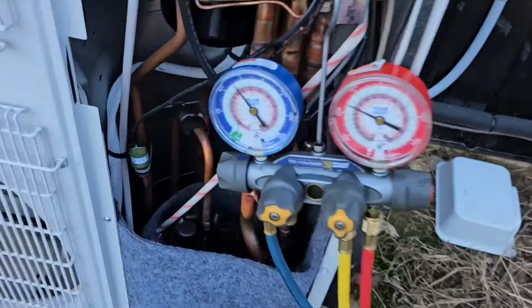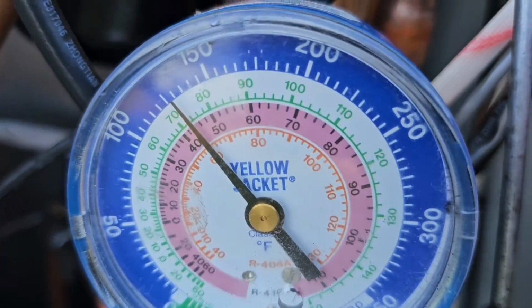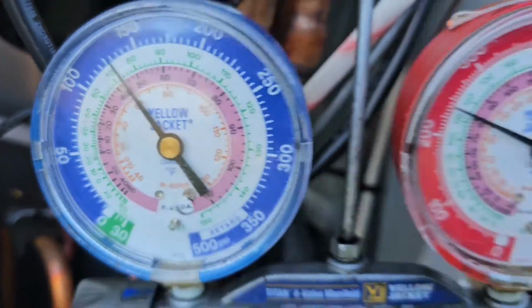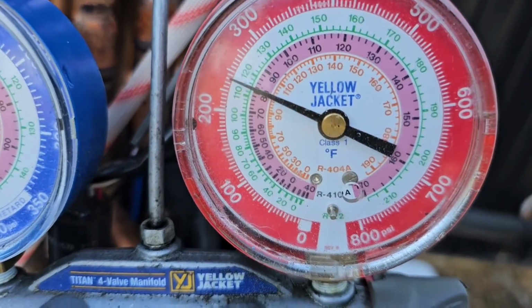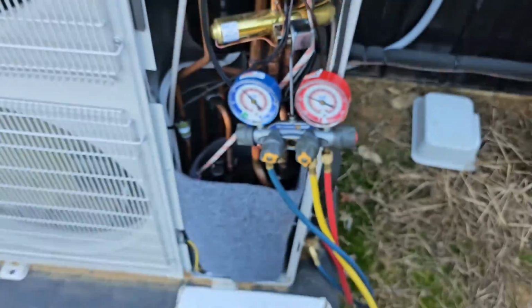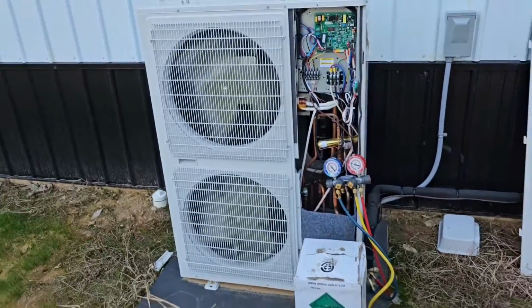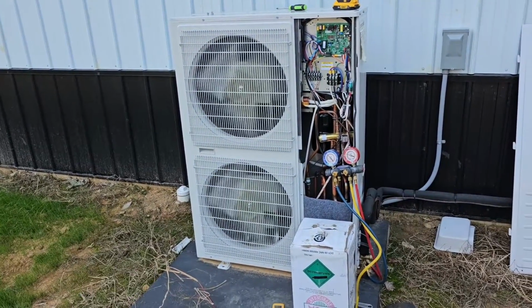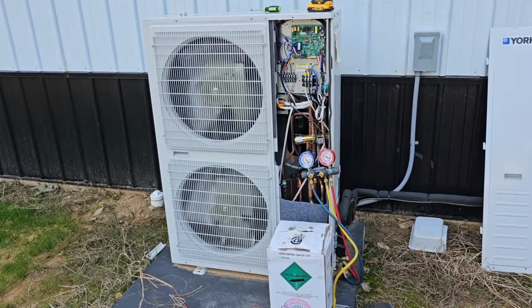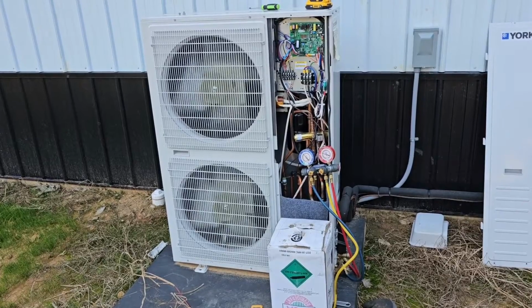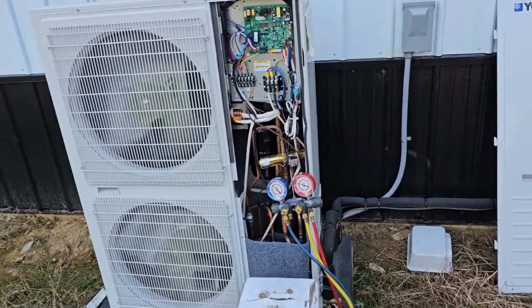We're going to measure the temperature split. We're going to measure the airflow. Let's check the pressures before we go inside. All right, pressure on the low side is about 130. High side is about 250. It's 240 right now. Perfect. Look at that, smooth. Not very loud. You can hear it ramping up though. All right, let's get some tools and go inside.